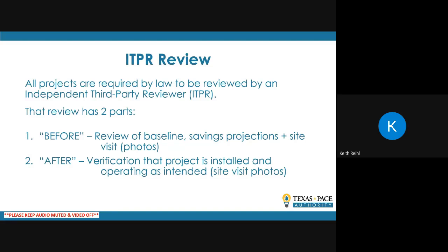After the project has been completed, you need to verify that everything was installed and operated as intended. So you need to have site photos, and you go out there and make sure everything's installed as it was planned. So if they said they were going to put 2x4 LED fixtures in, and you go out and it's 2x4 fluorescent fixtures, well, they didn't put in what they said. That would not be a good situation. But in most cases, you'll see they'll put in 2x4 LED fixtures. So again, after, you would take some pictures just to prove that everything was installed as it was asked for.